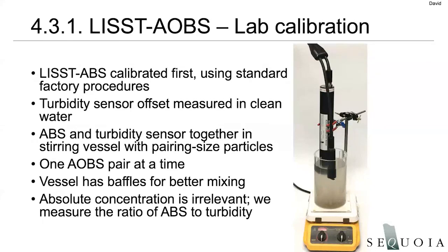The difference between the 30 micron particles and the 75 to 90 microns that we use for the other calibrations, having smaller particles helps quite a bit in terms of being able to keep them suspended. And also the fact that this pairing process doesn't require a precisely known concentration, because we're only looking at the relative response of the ABS and the OBS.